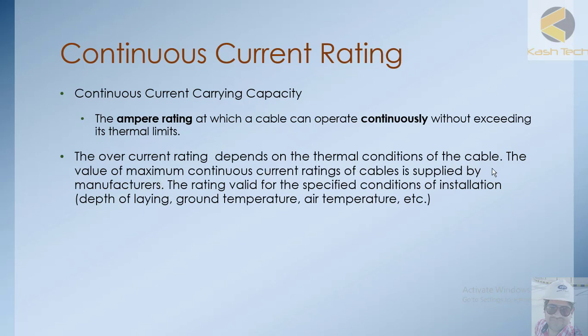The over-current rating depends on the thermal condition of the cable. The maximum continuous current rating is supplied by the manufacturer for specific installation conditions — depth of laying and ground temperature also affect the rating. For example, if a cable is continuously rated for 10 amperes but is bundled with 10 or 20 other cables, you cannot take 100% of that capacity. The cable capacity must be reduced by applying certain derating factors to find the actual real rating.